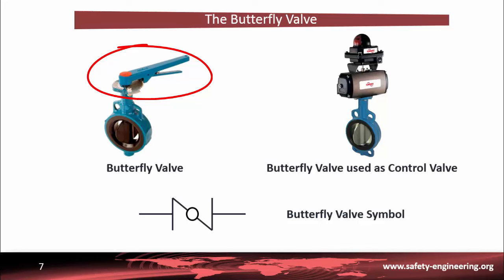The actuator spindle of the valve can also be attached to a lever for manual control. These valves are similar to ball valves but have several advantages: they are small and, when actuated pneumatically, open and close very quickly. The disc is lighter than a ball, and the valve requires less structural support than a ball valve of comparable diameter. Butterfly valves are very accurate, which gives them an advantage for industrial applications, and they are quite reliable and require very little maintenance. One disadvantage is that some portion of the disc is always presented to the flow even when fully opened, so butterfly valves always result in a pressure drop across the valve, regardless of the setting.